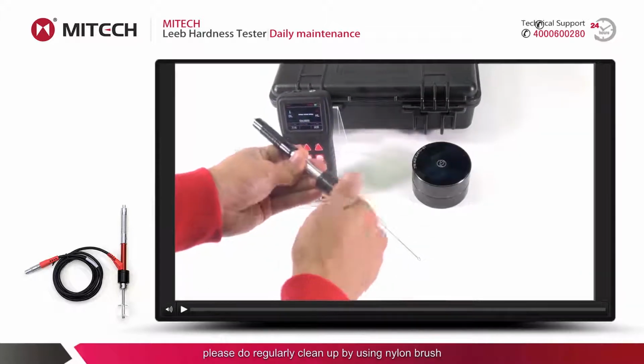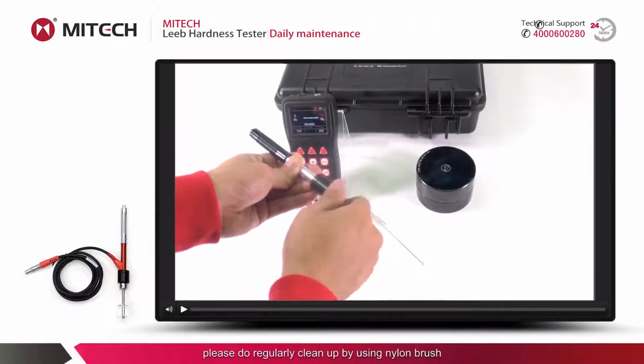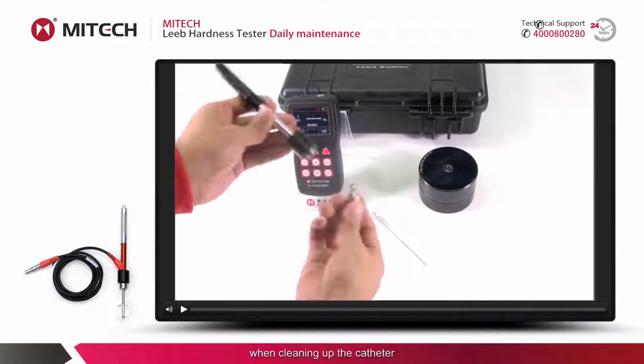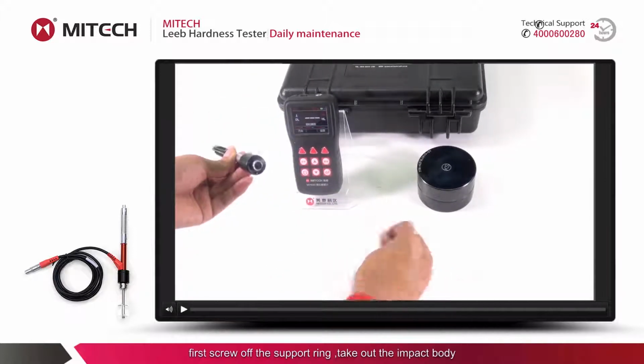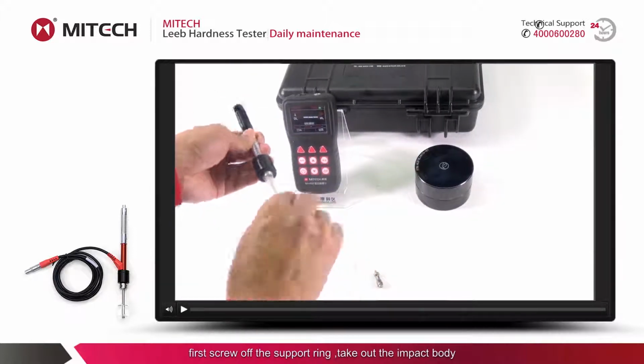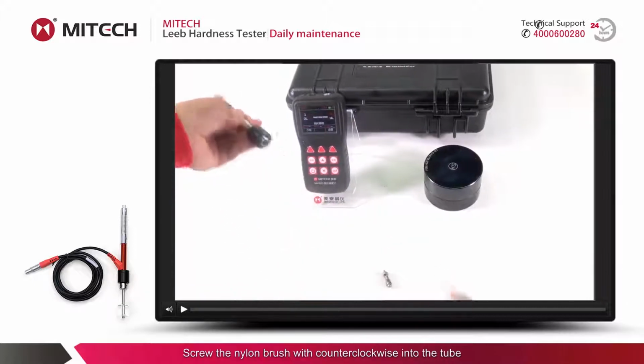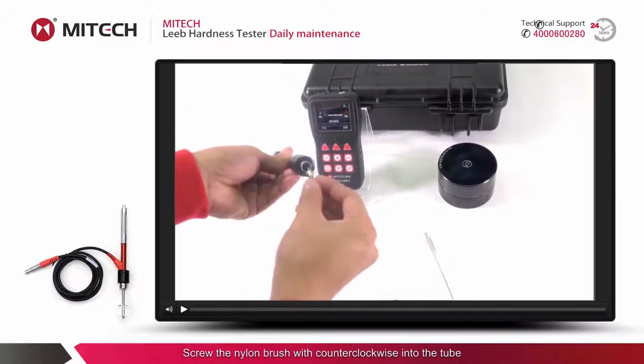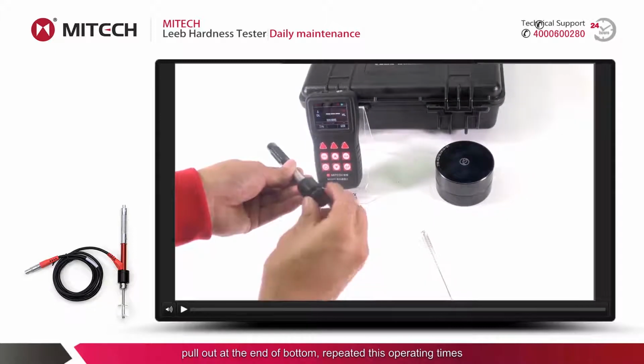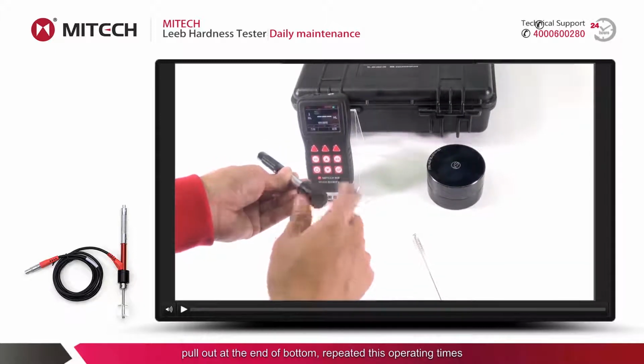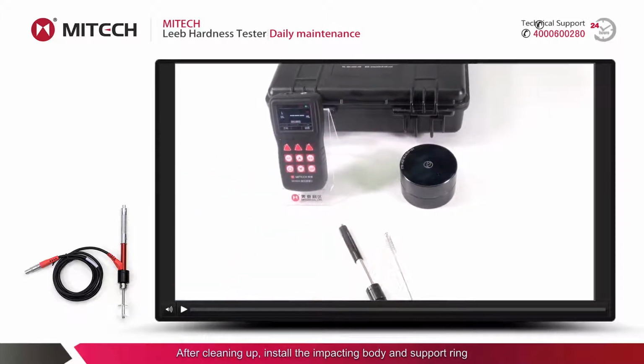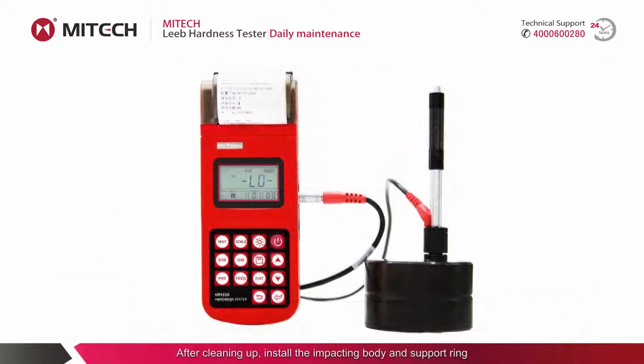For the catheter wall of the impacting device, please clean it regularly using a nylon brush. When cleaning the catheter, first screw off the supporting ring, take out the impact body, screw the nylon brush counterclockwise into the tube, and pull out at the bottom end. Repeat this operation several times. After cleaning, install the impacting body and the support ring.